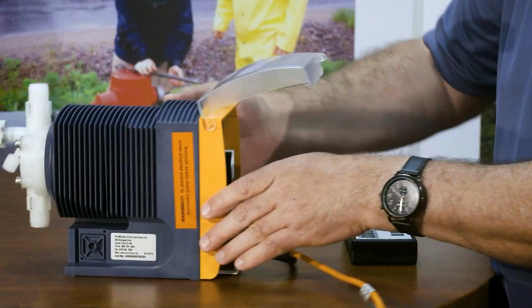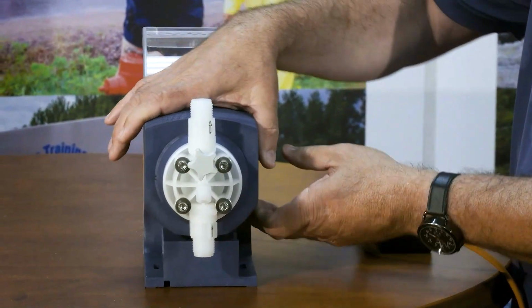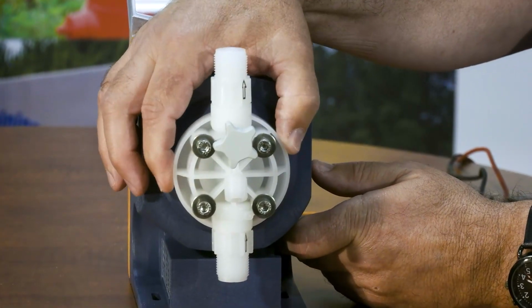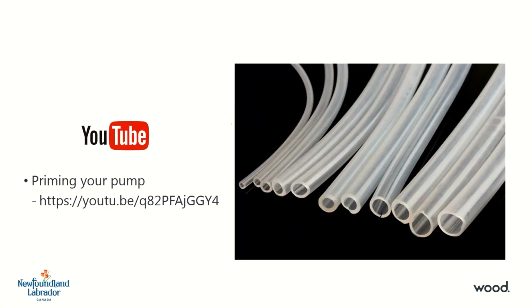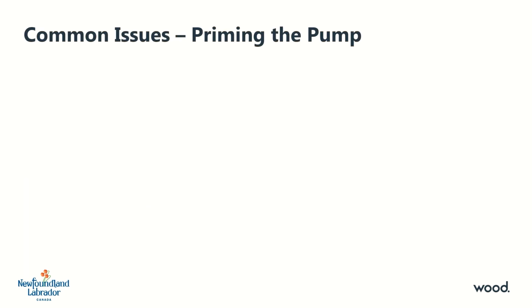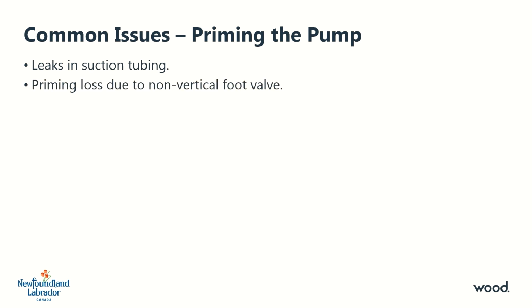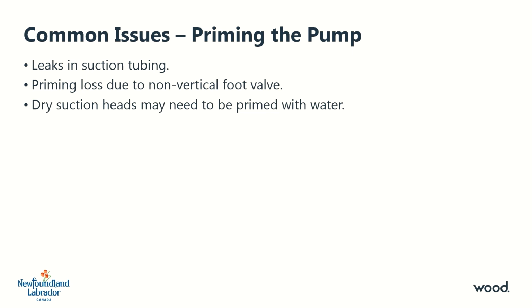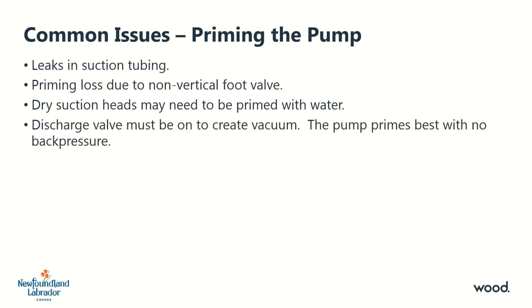If it is necessary to prime your pump, refer to the operations manual for the required steps. There is also information available on YouTube from equipment suppliers that provides detailed information on activities such as priming your pump. Some issues that can be encountered when priming the pump include leaks in the suction tubing, priming loss due to non-vertical foot valve. Dry suction heads may need to be primed with water. The discharge valve must be on to create vacuum. The pump primes best with no back pressure.